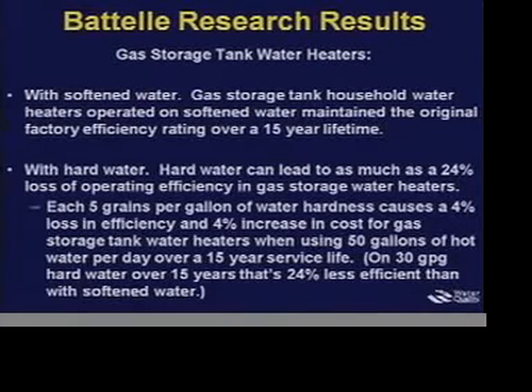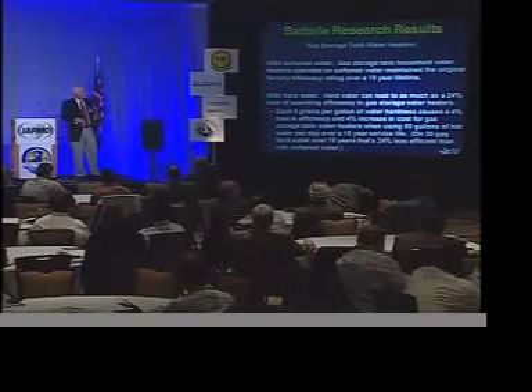For a summary of results for the gas storage tank water heaters: with softened water, these gas water heaters operated well for over the 15-year lifetime that the study simulated. With hard water, however, we used as much as 20% more energy — a 24% loss in energy efficiency. The energy loss starts right away: for each five grains per gallon of water hardness, there's about a 4% loss in efficiency and a 4% increase in cost. Assuming 50 gallons of hot water used per day over a 15-year life cycle, that could be up to 24% loss in efficiency at 30-grain water.